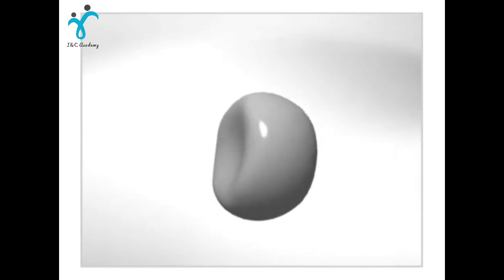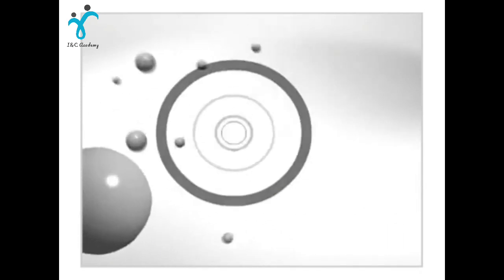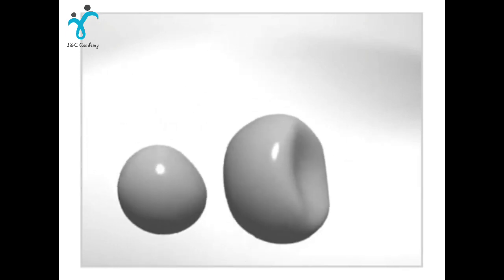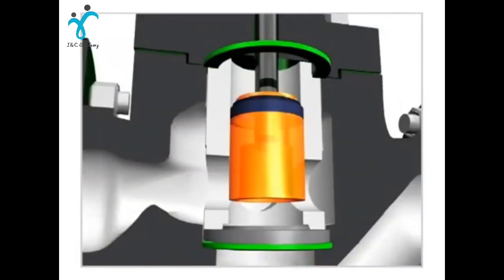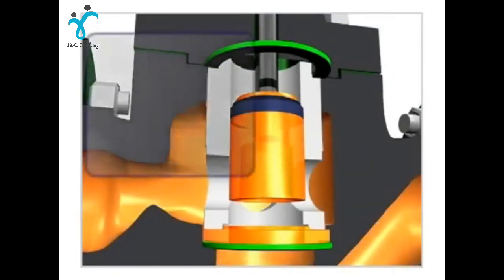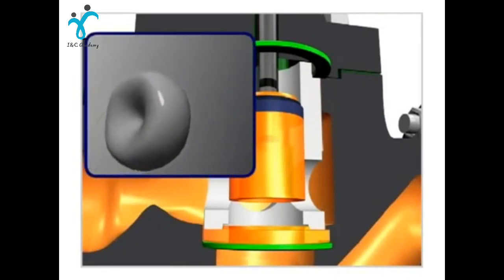These implosions can also cause local pressure waves of up to 100,000 pounds per square inch. The combination of pressure waves and microjets can cause severe damage to the valve plug, seat and body when they're located near the material surface.